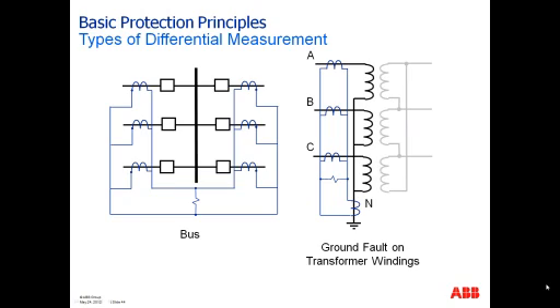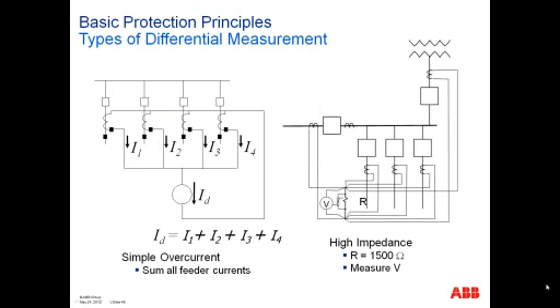Types of differential measurement you have. Here I show where the number of buses are all summed up. The ground fault on transformer windings, that's commonly used today, is referred to as restricted earth fault detection, but you measure the current in A, the current in B, and the current in C. They should add up to whatever 3I0 is, and you compare that quantity with the actual 3I0 flowing in the neutral.